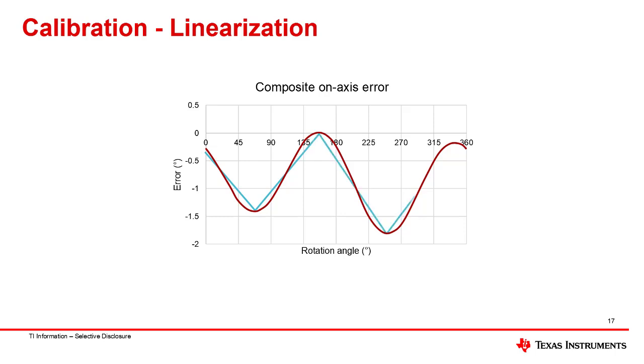For example, a four-point calibration might be accomplished by determining the peak error locations and making linear approximations to correct the error. The resulting post-calibration error shows a significant improvement. A calibration of this nature will improve with greater number of linearization points, as the approximation begins to more closely fit the real error.